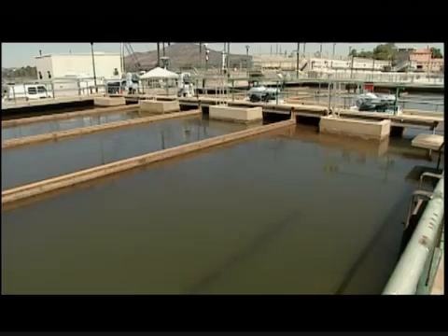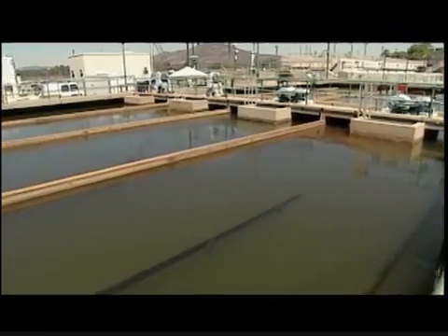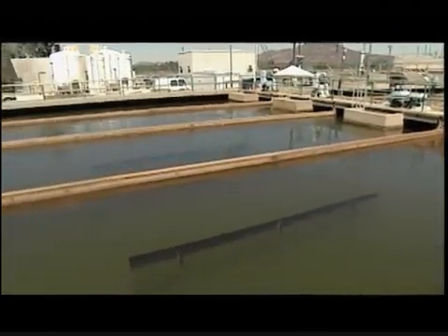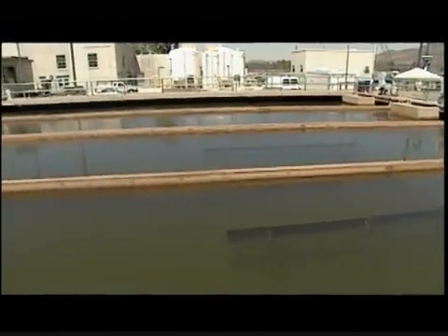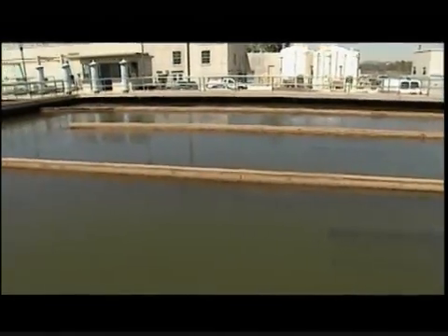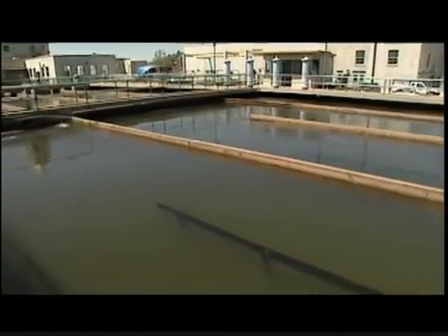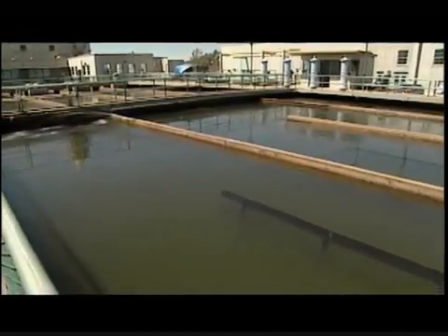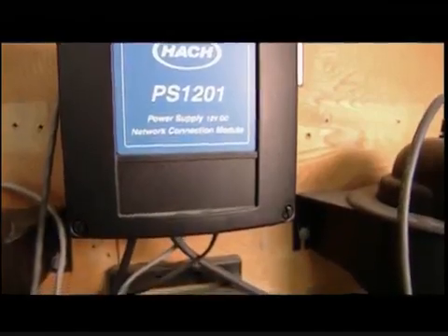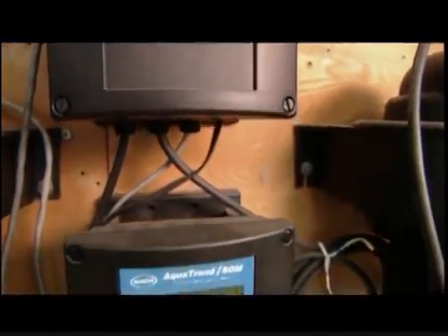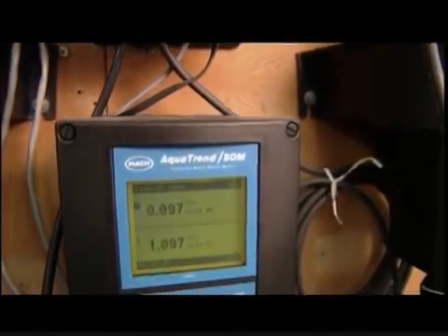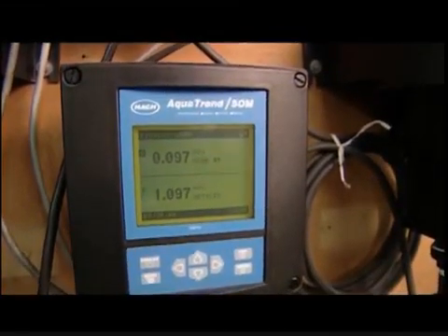For some coagulants, alkalinity is a factor. Operators may need to raise alkalinity for coagulation to be effective when using iron or aluminum coagulants that can consume alkalinity and depress pH when they are added to low alkalinity waters. Turbidity is also important. The lower the turbidity, the more difficult it is to form proper floc.